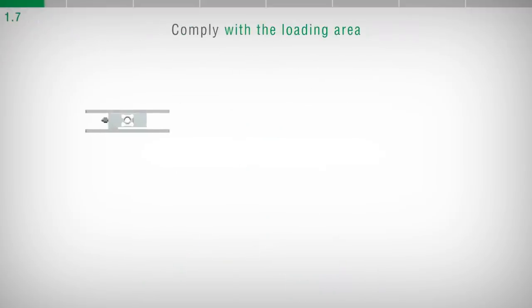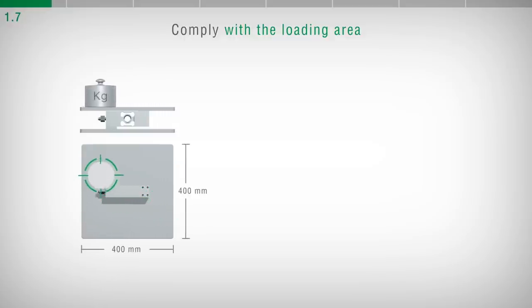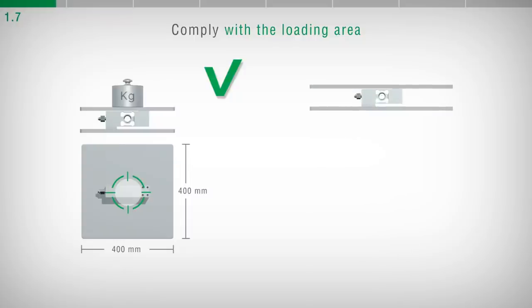Single-point load cells are able to weigh correctly within an area stated on the data sheet. For example, using a load cell guaranteed for an area of 400 x 400 mm, we are certain that by applying a weight force at any point of a structure of such dimensions, the detection will be correct.